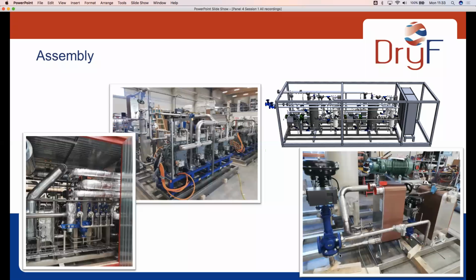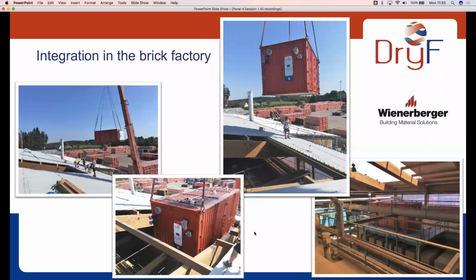And here I have some impressions from the construction and assembly work of the heat pumps. On the left, in front, you see the module consisting of 4 piston compressors provided by Viking Heat Engines. And in the picture on the right, there's a compressor in green. That's the screw compressor from Bitzer. The heat pump itself is designed as a container module. So it was manufactured on the site of our manufacturer, and then it was transported to the brick factory, lifted into the factory via the roof, and it's located on top of the tunnel dryer on a platform, and there it was connected to the process.